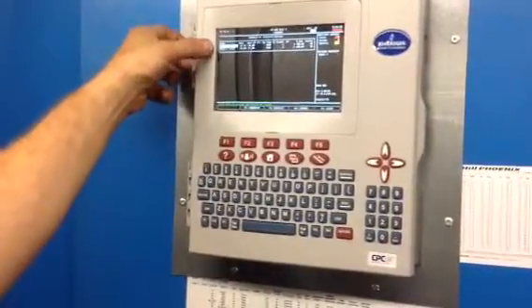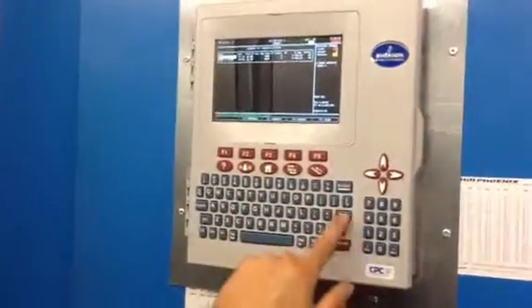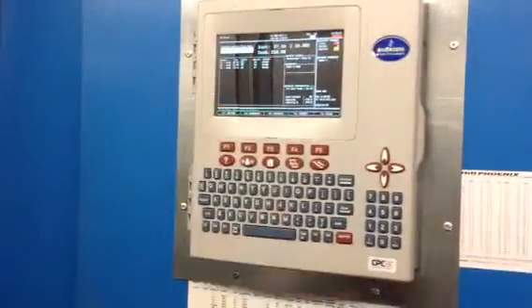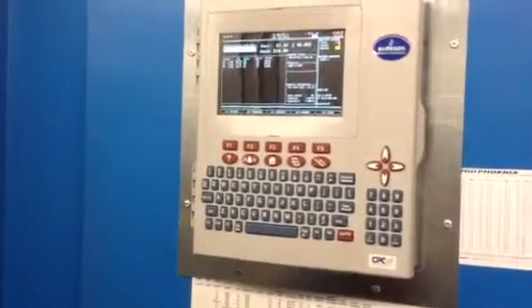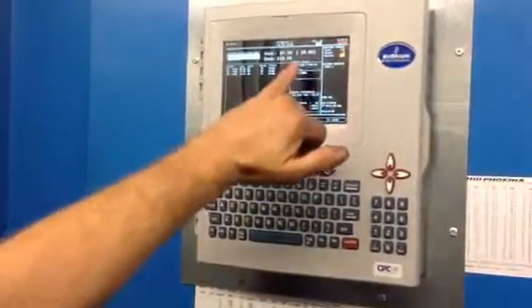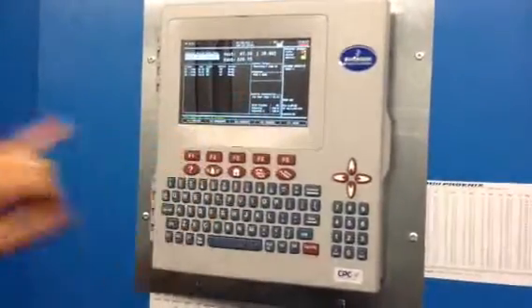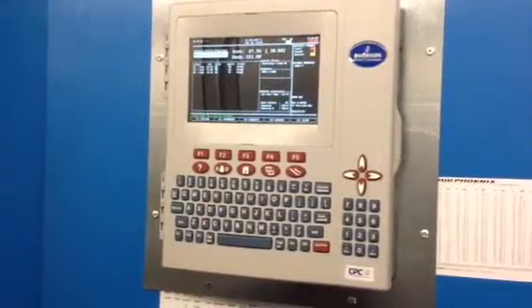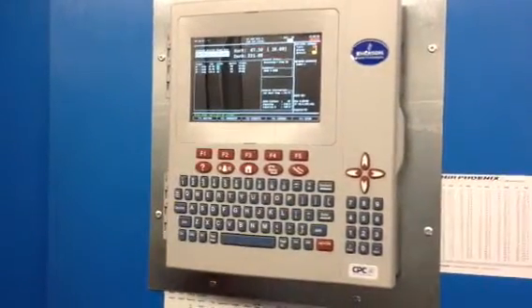What rack are we on? Rack 4. Highlight rack 4. We're running 47 pounds. Now you notice we have a 38-pound set point. I have a couple of compressors off just for demonstration purposes only.